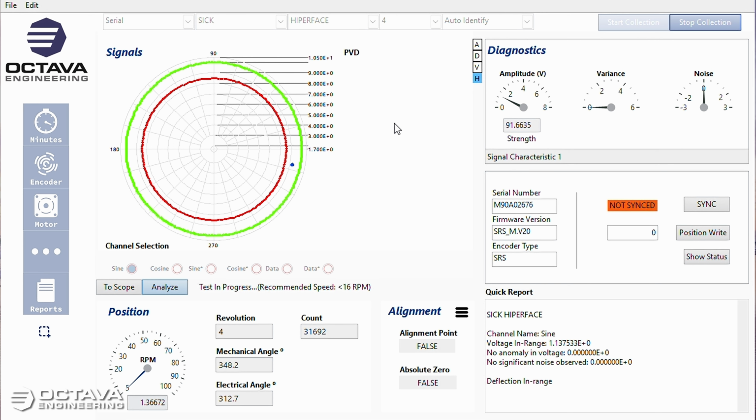Most commonly, it would be the result of internal environmental contamination, like oil contamination, dirt, dust, smudges, anything like that on the glass disc itself, causing basically a read error between the glass disc and the photodiode. It can also occur if that disc is tilted, if the gap is set incorrectly.